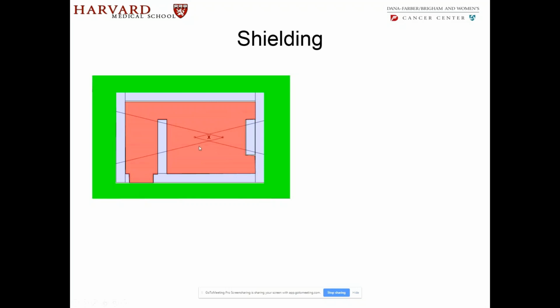Ideally, you would want the Linac positioned so the gantry rotates along this direction, so that the control system and offices don't need a lot of shielding, because radiation is coming out mostly in the other direction and this side would only get scattered radiation. Unfortunately, our bunker didn't allow that.